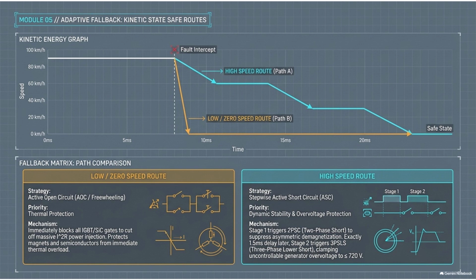The uncontrolled generator is still generating electricity, but instead of that voltage blasting backward into the delicate electronics, the electrical current simply loops round and round within the thick copper stator coils. It forces the motor to basically swallow its own poison. That is a brilliant way to phrase it. The heavy copper coils have enough thermal mass to safely absorb that energy. By trapping the current in this short-circuit loop, the system physically clamps the deadly voltage spike to a safe limit, usually 720 volts or less.